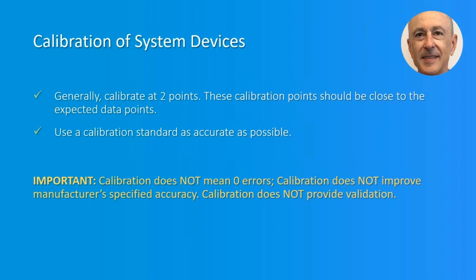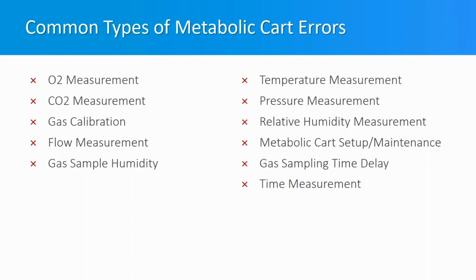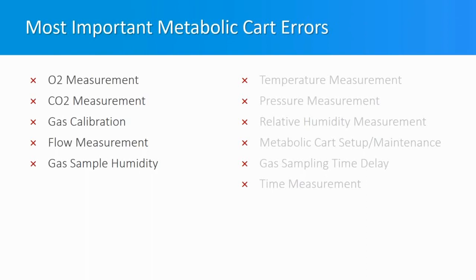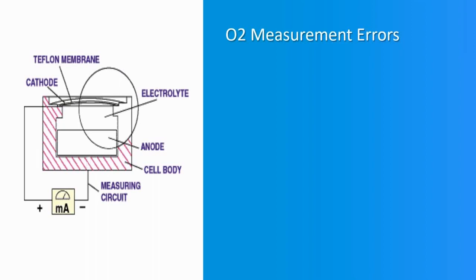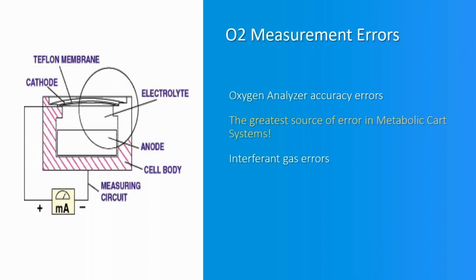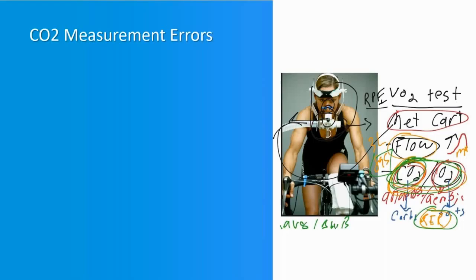Each of these physical measurements and other factors has an error associated with it, and there are quite a few potential errors. The oxygen analyzer accuracy is the greatest source of error in metabolic cart systems. All gas analyzers are affected by interferent gases — unknown or unexpected gases in the ambient air — which will produce an unwanted response from the oxygen analyzer. Having a room with fresh outside air will minimize this problem.